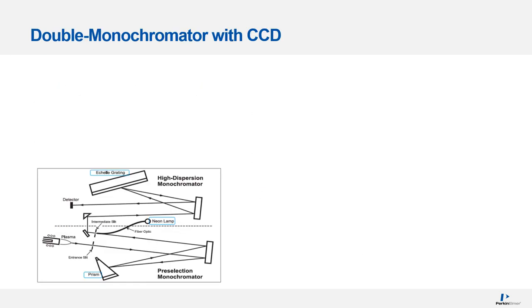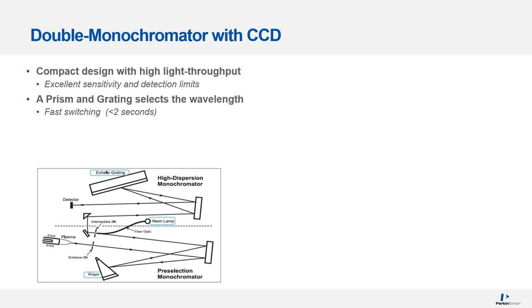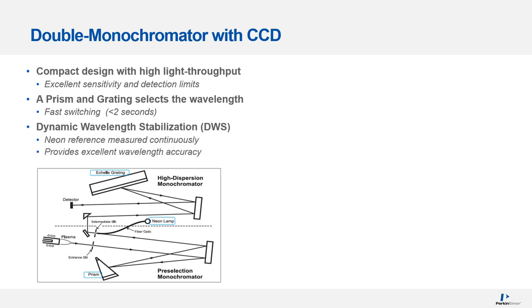The Avio 200 has a unique double monochromator optical design with a CCD detector. This is a compact system with high light throughput that provides excellent sensitivity and detection limits. A prism and a grating determine what wavelength is focused onto the detector, and they can move quickly — in less than two seconds — when changing wavelengths. It also has a system called dynamic wavelength stabilization: a neon lamp introduces a neon reference beam into the light path at the intermediate slit, which is measured continuously by the detector, correcting for any spectral drift and providing excellent wavelength accuracy.